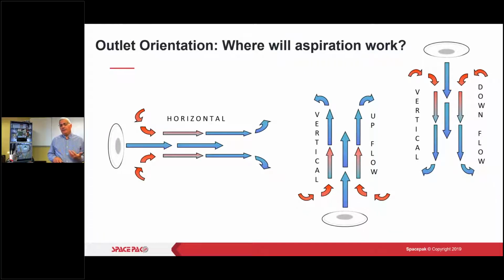Now, if you're thinking, what do I get out of these outlets when it comes to heating and cooling? You basically are getting 2,000 BTUs out of each outlet when it comes to cooling, 3,000 BTUs out of each outlet when it comes to heating. Depending on what this system is going to be doing, if it is primary heat and cool, more than likely your heating load will be higher, so you'll have to size your outlets and the amount of drops per room based on that design. If it's just going to be cooling, then you know how many outlets you'll need per room based on that load per room, 2,000 BTUs, and you can size your outlets accordingly. So if you come up with something that's 1.5 or 2.5 outlets, you always have to bump it up. There is no such thing as a 1.5 outlet.